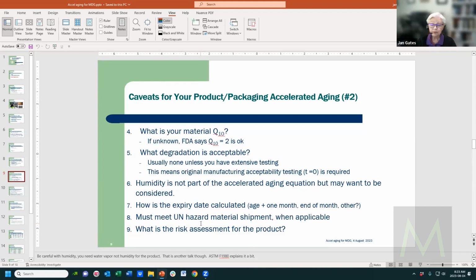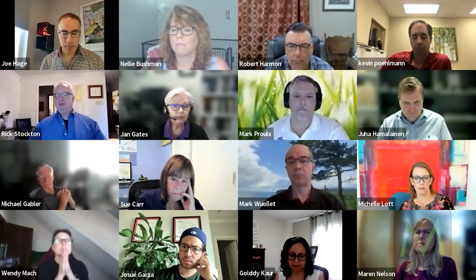And then if you are shipping something that's considered hazardous, you also have to do some UN testing where it's applicable. And that's not the same as the performance test that we usually do to make sure a product in a package is acceptable, because the UN is only worried about the hazardous material leaking out of your package and making somebody sick. They don't care if it's actually functional or not. They just make sure it's not leaking. So you have to do a different set of performance tests with your aging and everything else that's going on to make sure that everything functions properly. And then make sure you understand your risk assessment, because if it doesn't really matter if a product cracks or something, you need to account for that when you're doing your testing and put that in there as an acceptable thing to happen.